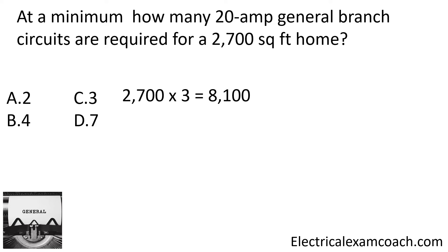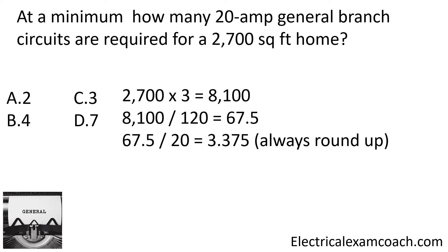Because this is our general lighting, those are all going to be 120-volt circuits. So we take that 8,100 and divide it by 120 volts, which gives us 67.5 amps — we're converting it over to amps. Then we take that and divide it by whatever size branch circuit we're installing. In this case, they want to run 20 amp circuits. We take our 67.5 divided by 20, which gives us 3.375 circuits. We're always going to round up because you can't have a piece of a circuit, so the correct answer would be four for this home.